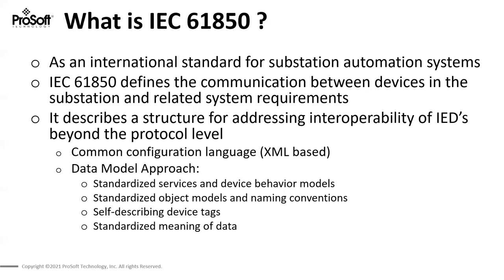Even those protocols came up short in some areas. The protocol we see rising quite a bit, and the preferred protocol used in these applications, is IEC 61850. It's a newer standard that's helped address the shortcomings of the other protocols. IEC 61850 is basically an international standard for substation automation. It defines not only the communication between devices, but also describes structured support for interoperability between various IEDs. They went so far as to define a common configuration language.